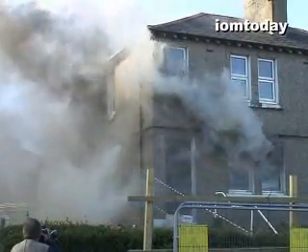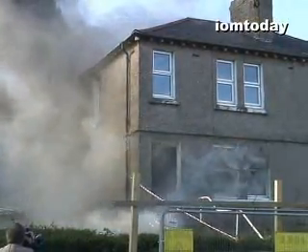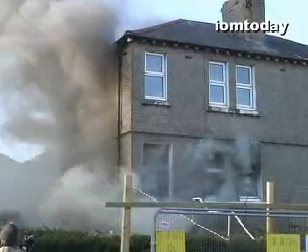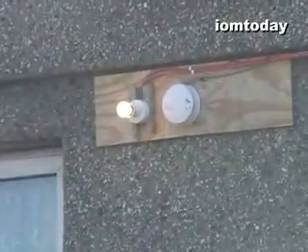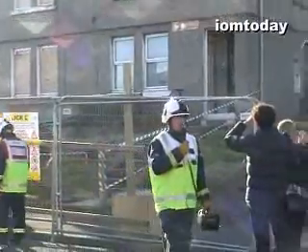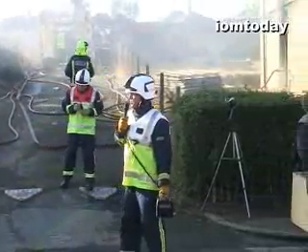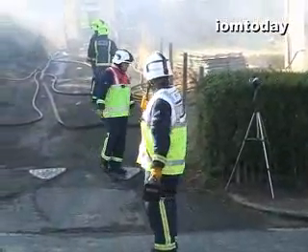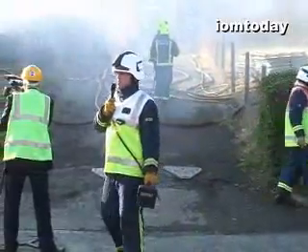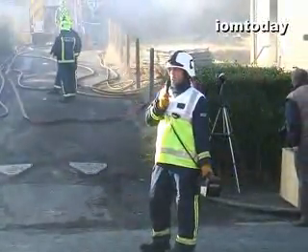I'm sure that anybody watching here would agree — it's quite distressing what's going on, especially if this was in the middle of the night and you were upstairs. The light has come on in number five, which signifies that sprinkler has at last operated. The smoke detector was also operated by the severe fire in number seven. Now some people say that sprinklers are expensive, not needed, a bit over the top, that they flood the house, or raise concerns about legionnaires and stagnant water. My argument would be: please look at number five and please look at number seven afterwards, and then tell me that a sprinkler system is not the best system to put in a domestic property for both life and property safety.